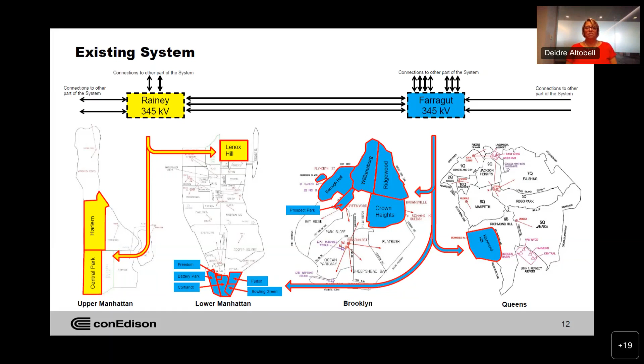This slide shows the Con Edison system with the Brooklyn Clean Energy Hub. The hub is located between Rainey and Farragut, intersecting the 3 feeders that currently connect Rainey to Farragut, creating 6 345 kV feeder outlet connections. Additionally, there are 2 other outlet feeders that were relocated from Farragut. As the offshore wind injections depicted in red connect to the hub, the power can be transferred to other parts of our system through the newly created outlet feeders. Additionally, we intend to transfer the Lower Manhattan load that is currently served by Farragut to the hub so that it can absorb wind injections.